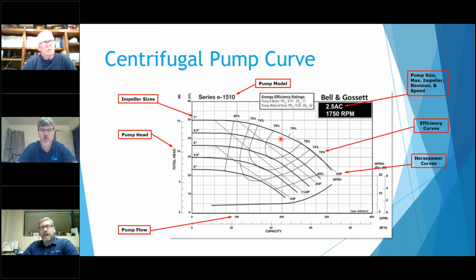These little half moons or arcs are the efficiency curves. You do want to try to be at the best efficiency point. It is the best place to operate, because it's where the pump is most efficient. It's also the point where the pump vibrates the least. The further you get out in this direction, and the further you go out in this direction, the pump will vibrate more. So if you can stay in the best efficiency point area, it reduces the likelihood of that happening.